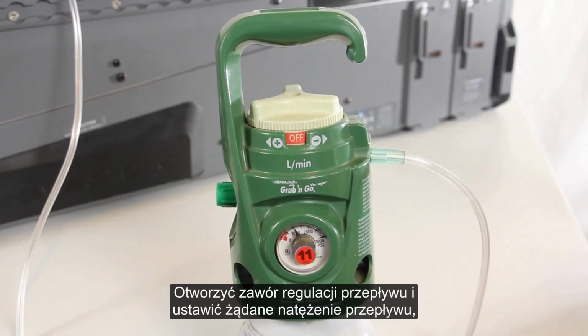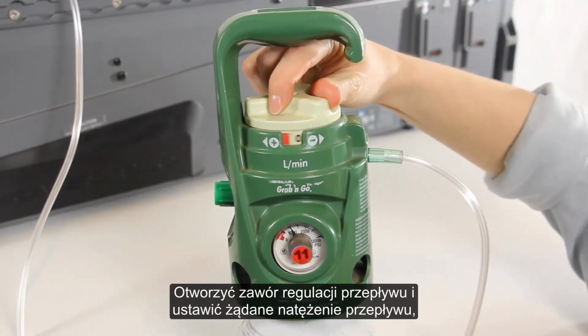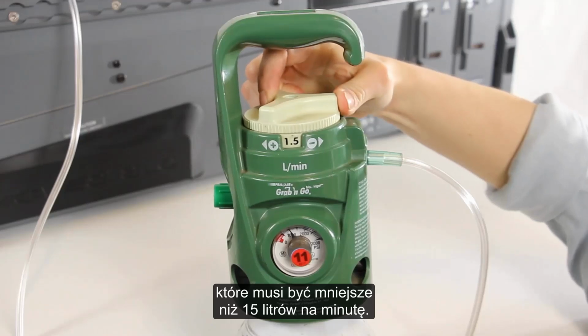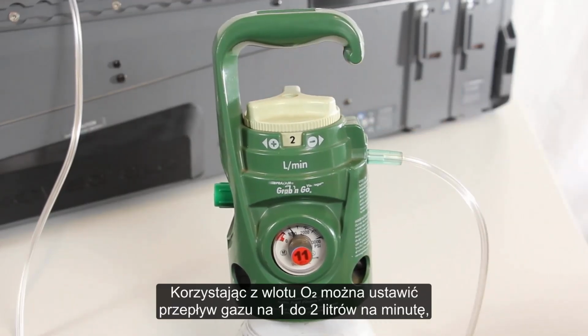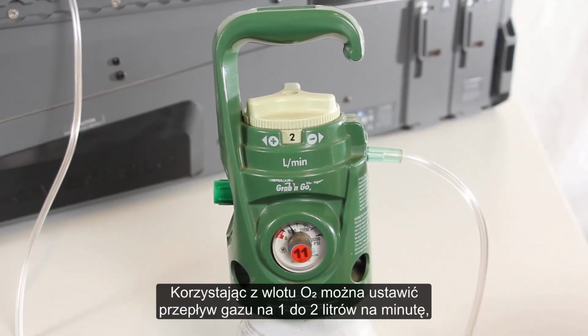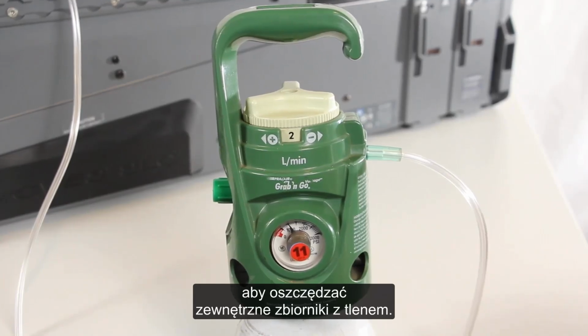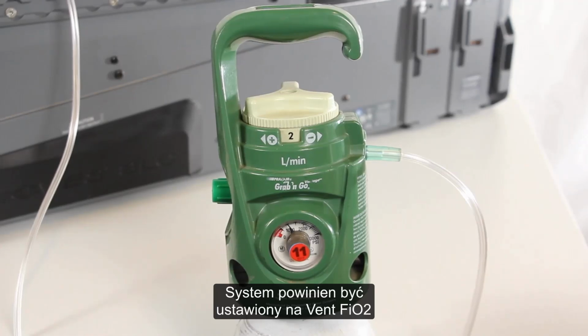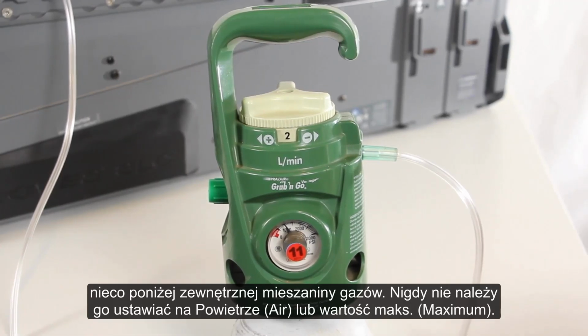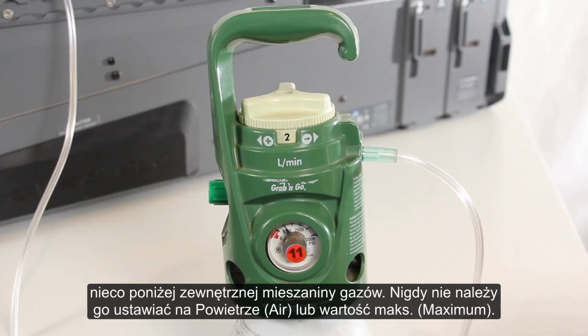Open the flow control valve and adjust to the desired flow rate, which must be less than 15 liters per minute. When using the O2 inlet, gas flows of 1 to 2 liters per minute can be used to conserve external oxygen tanks. The system should be set to vent FiO2 slightly under the external gas mix and never set to air or maximum.